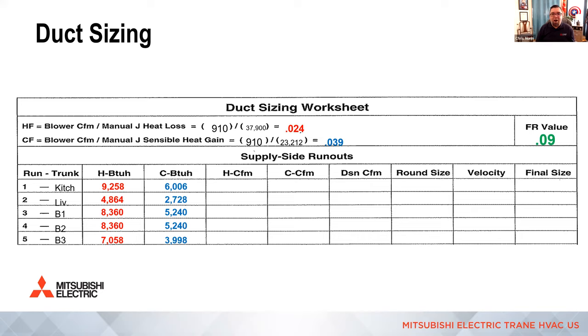All right. Of course, simple math here, heat loss for the kitchen times heating factor gives me heating CFM. And another rule of duct design, like I talked about earlier, if it's over 200, split that into 2 runs. For this worksheet, we're just going to keep it simple for class purposes. Cooling gains for that kitchen times the cooling factor gives me cooling CFM. Now, in this example, we're going to design around the cooling CFM needed for the kitchen, which is 234. So larger of the two, right? 234 CFM at 0.09 on our duct calculator gives me an 8-inch run.